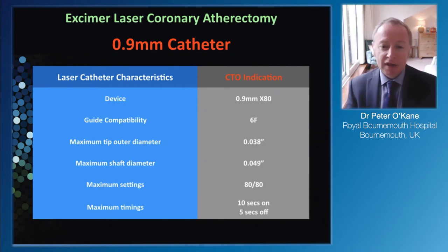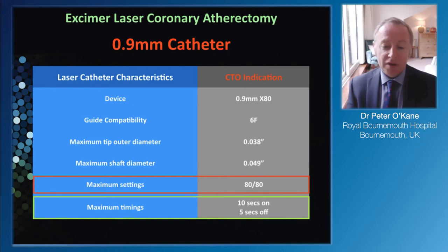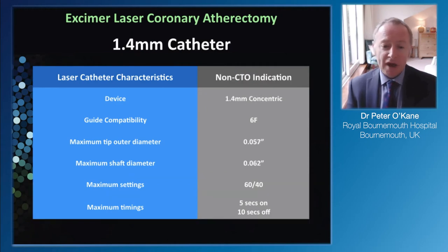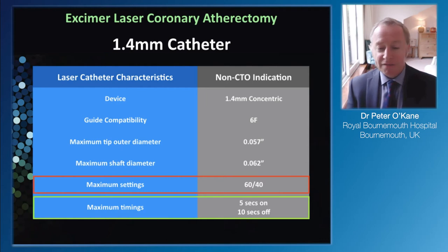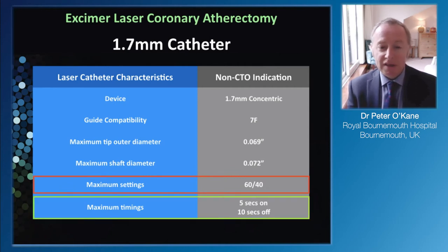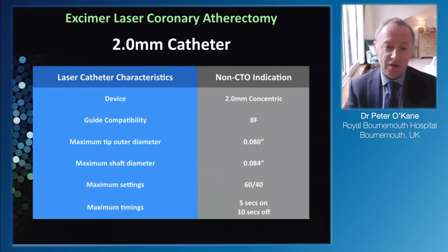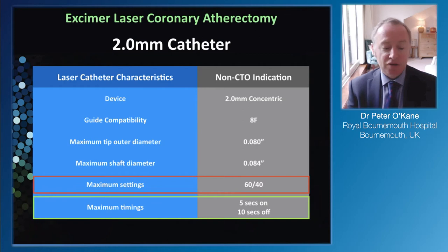There are four types of laser catheter commonly used in the coronary circulation. The 0.9mm is the most commonly used - six-French compatible. I like it for two reasons: it gives maximum energy deliverable at 80/80, and maximum lasing time of 10 seconds on with a five-second rest period, making the case faster. The 1.4 catheter is also six-French compatible but maximum settings are only 60/40, so less good in CTO setting, and gives only five seconds of lasing with an automated ten-second rest. The 1.7 catheter is seven-French compatible. Finally the 2.0 catheter is eight-French compatible, used for big arteries with thrombus.